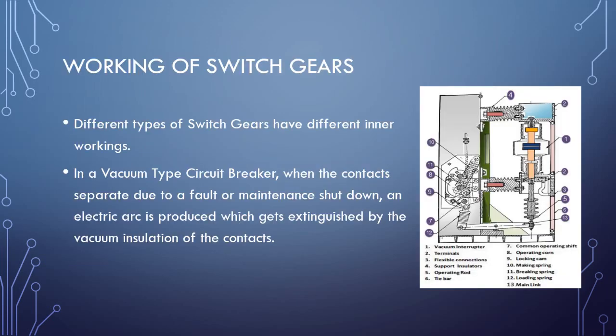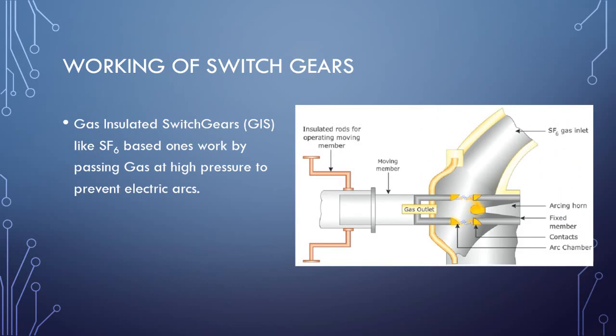Working of switchgears. Even though all switchgears have the same purpose, different types of switchgears have different mechanisms for breaking the circuit. The main problem is electrical arcing, which occurs when two highly energized conductors or contacts separate. Electrical arcing is the electrical breakdown of a gas that produces an electrical discharge. It can damage the internal components of the switchgear and cause fires. Vacuum switchgears tackle this by insulating the contacts in vacuum. No arcing can occur if there is no gas to ionize. In SF6 switchgears, sulfur hexafluoride gas is passed over the contactors when they are separated in order to absorb the ionized particles and thus prevent the electrical arc from forming.